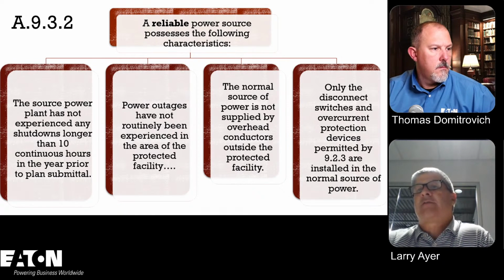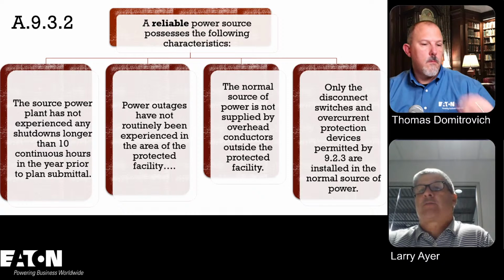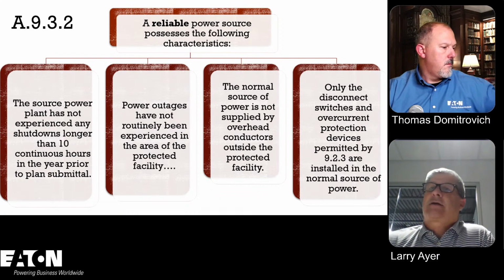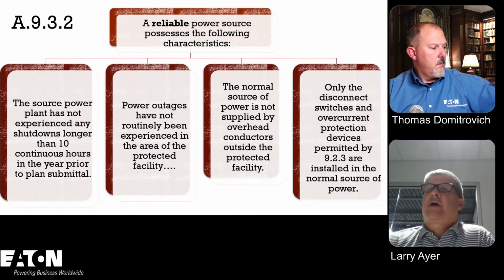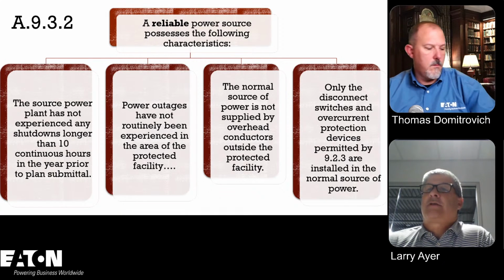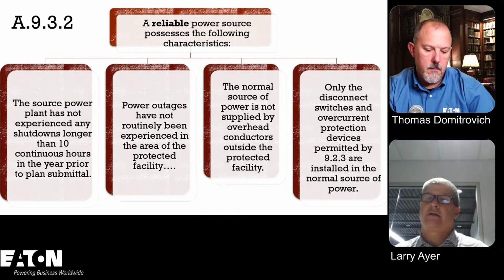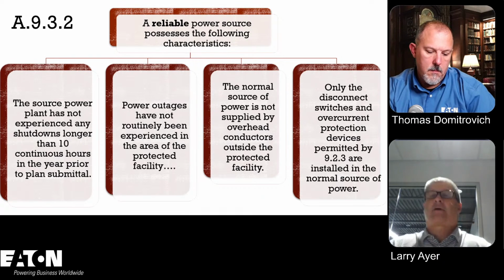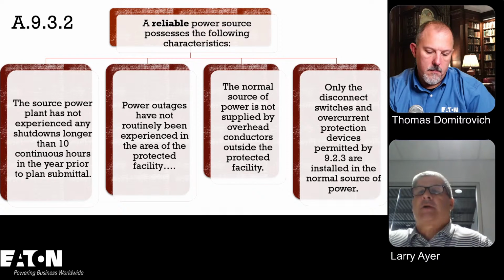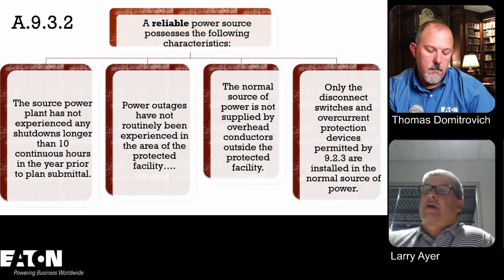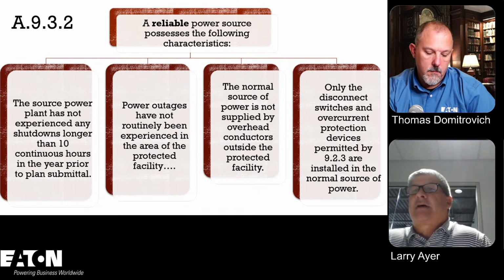They give you four different situations here. If the source power plant has experienced any shutdowns longer than 10 hours in the year prior to plan submittal, then it's considered not reliable. Number two: power outages that have been routinely experienced in the area of the protected facility. I think that's probably written wrong in the slide. Number three: the normal source of power is not supplied by overhead conductors. Overhead conductors are more susceptible to falling tree limbs and things of that nature.